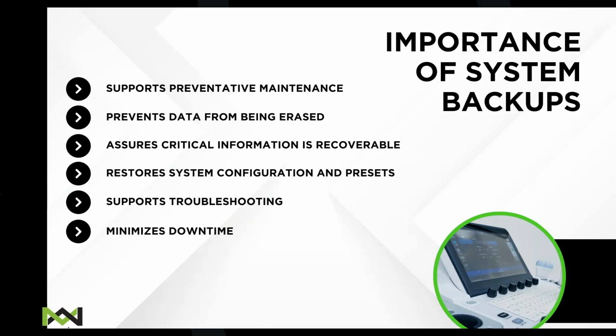The importance of ultrasound system backups. A lot of times when I get calls for tech support, whether the system has an error code or is down, one of the first things I ask for is if there's a good backup of the system. And that is for recovery purposes.